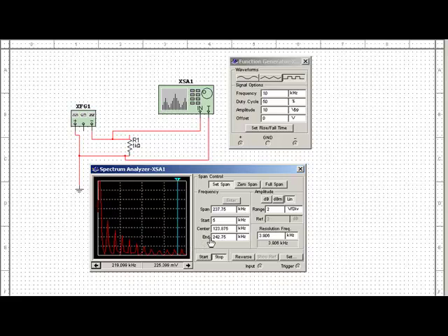We're graphing out to 242 kHz. And like I said, there are just limitations of how much I can display. If I put this up really high, then these get so crunched together that it's hard to decipher what's what. But anyway, we just wanted to display the ability to look at the fundamental and all of the harmonics.